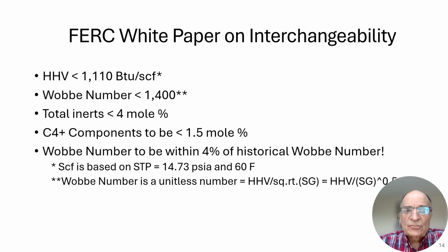Let's move away from hydrogen for the moment and talk about interchangeability of natural gas send out. Remember, natural gas, which comes from vaporizing LNG, needs to be interchangeable with pipeline natural gas. Now, there are no hard and fast rules for that because the natural gas composition is different all around the country. But FERC, the Federal Energy Regulatory Commission, did put out a white paper that most people use as their guidelines.